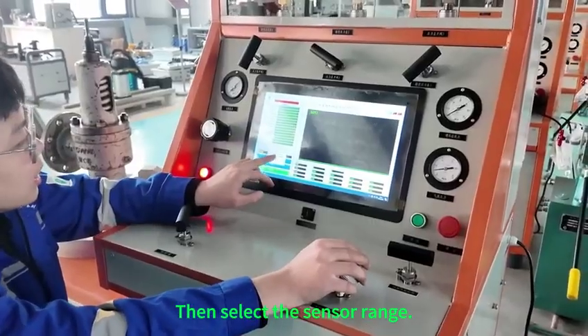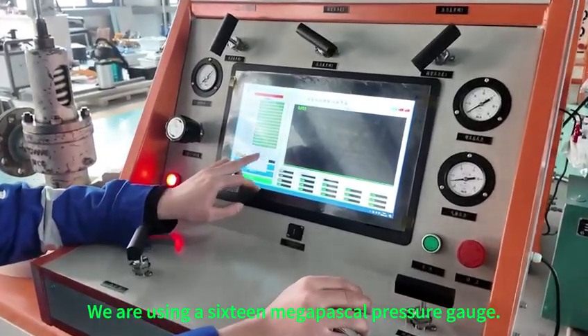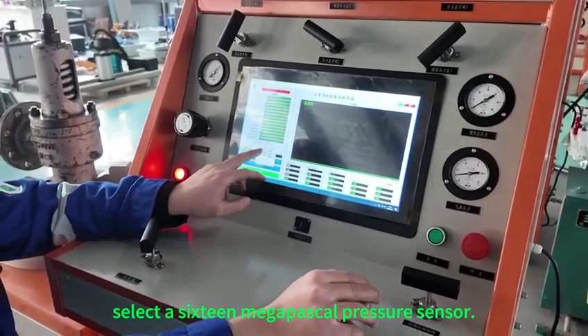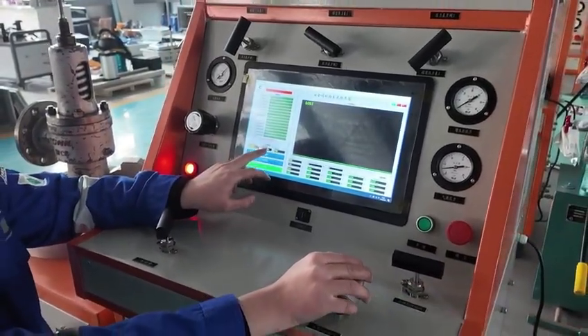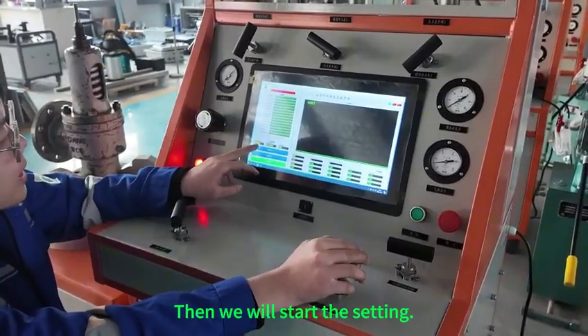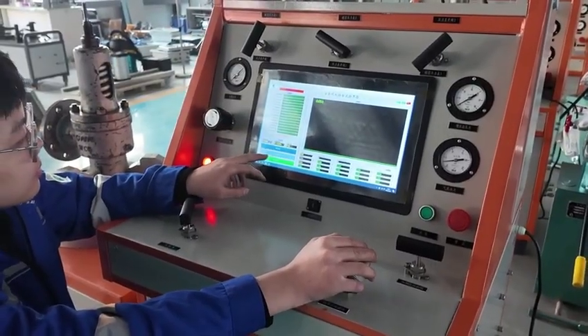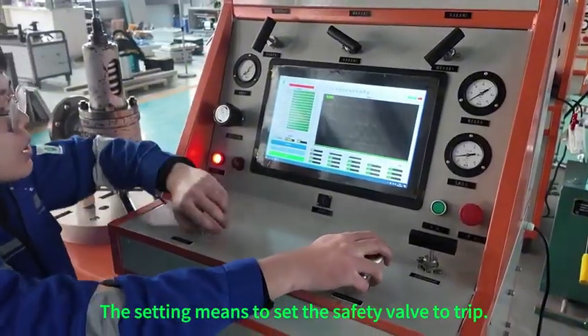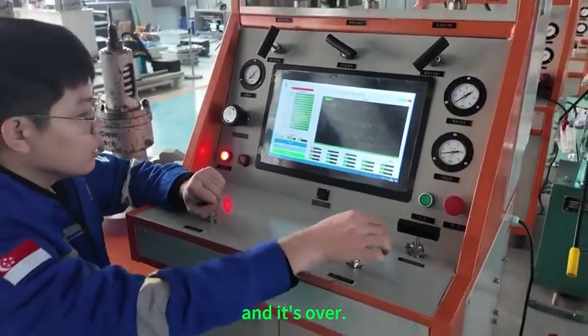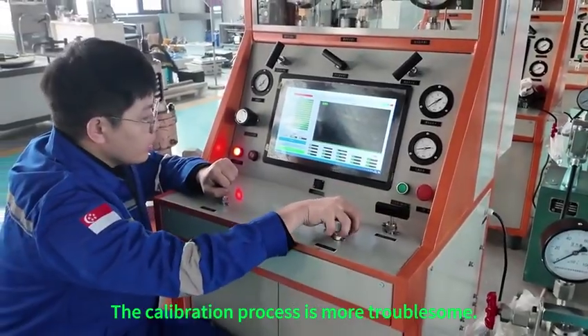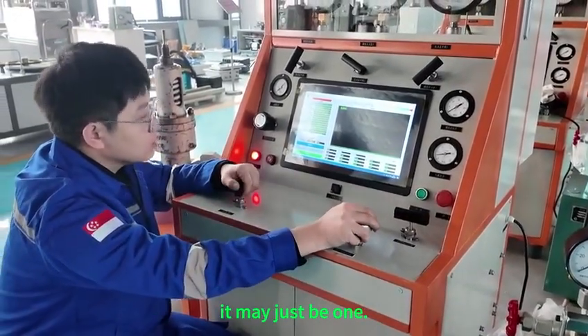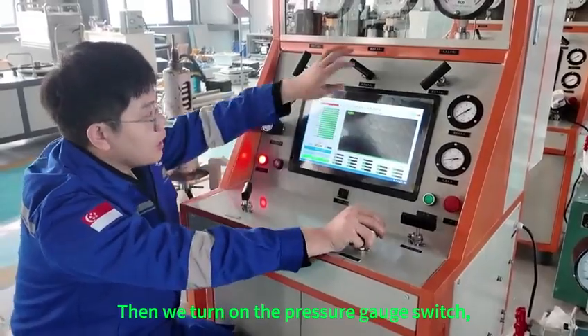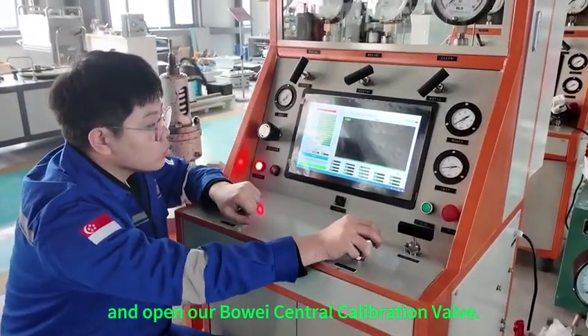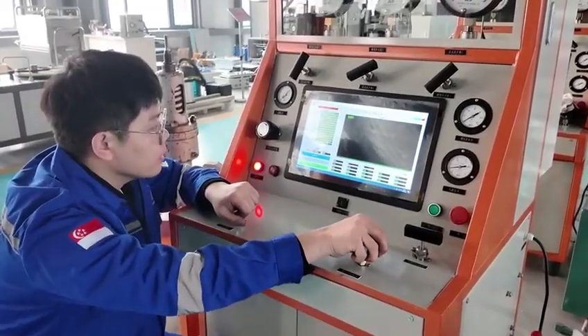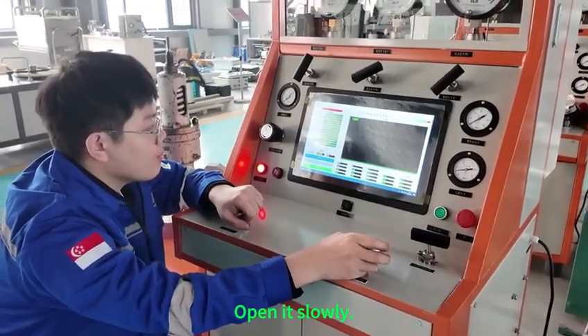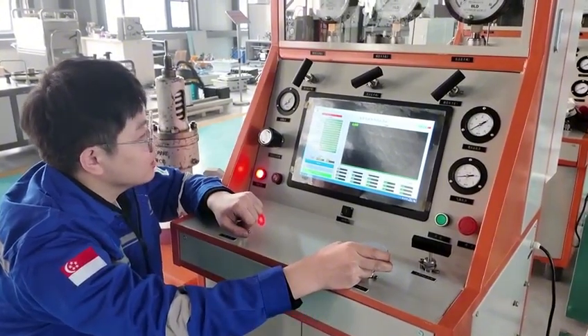Then select the sensor range. We are using a 16 megapascal pressure gauge, so select the 16 megapascal pressure sensor. Okay. Then we will start the setting. The setting means to set the safety valve to trip, and the calibration process is more troublesome. Then we turn on the pressure gauge switch and open our central calibration valve. Open it slowly, and don't open it too fast.